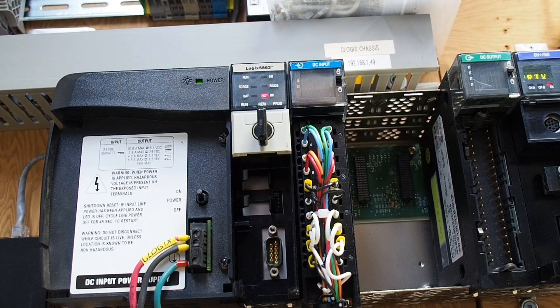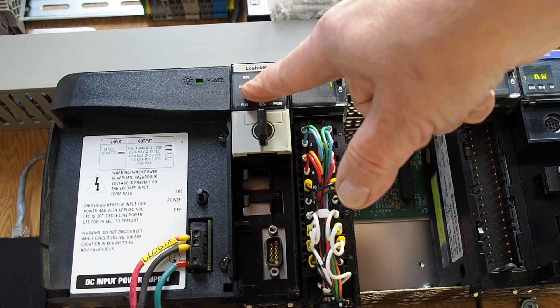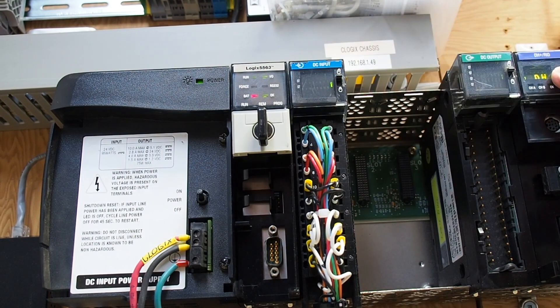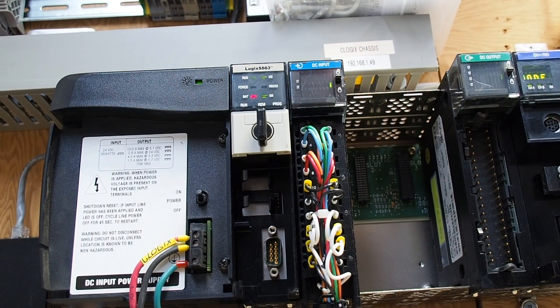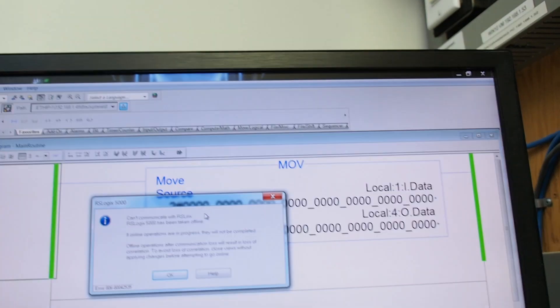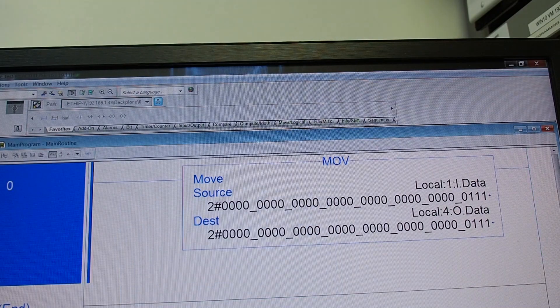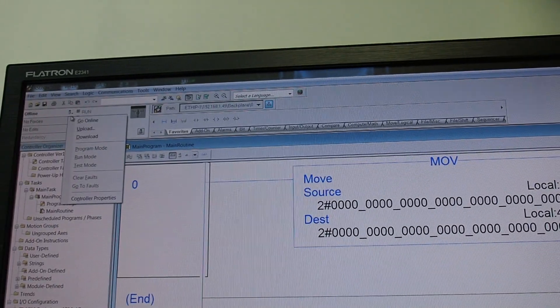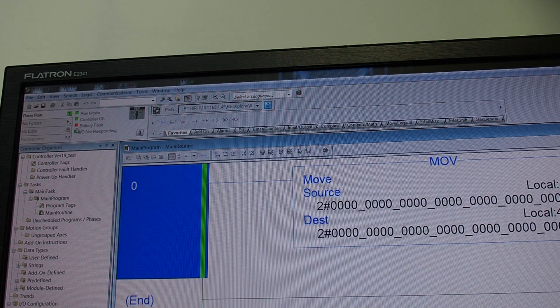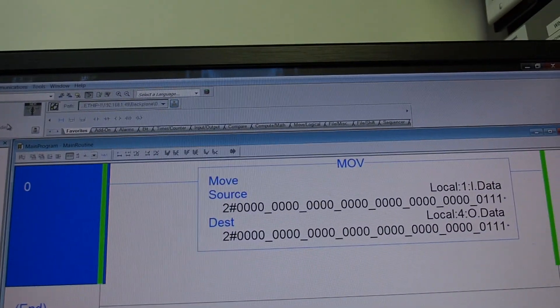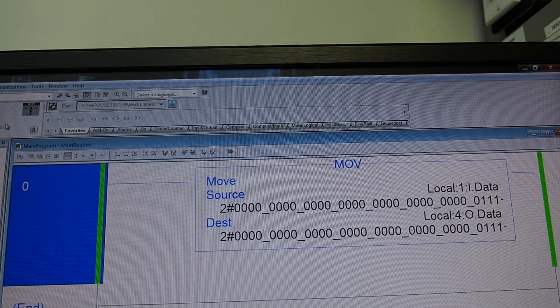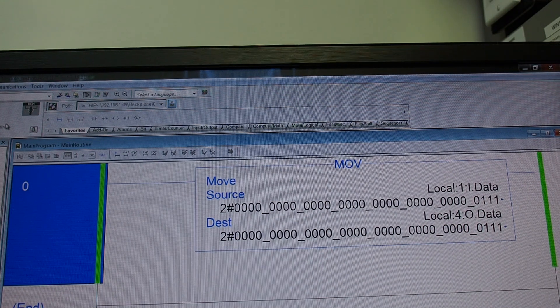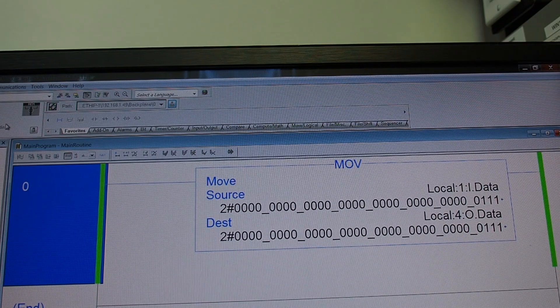But because we have the CF card in the settings as shown earlier, it starts up in run mode right away. We've got the flashing light just because of the DHRIO card I haven't got that set up properly. So there it is running so we'll turn on a couple of inputs. We are offline because we went offline, can't communicate, okay. Go online. We see immediately that we're online, we see that our IO is following as it should be. That's as easy as it is to set up a CF card and make it come back up and run without a battery or a power fault every time.